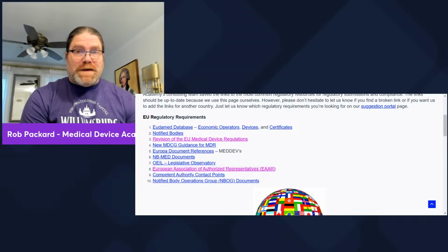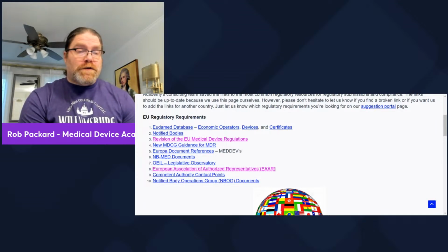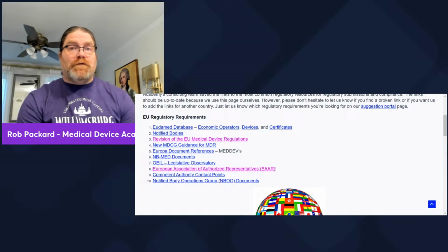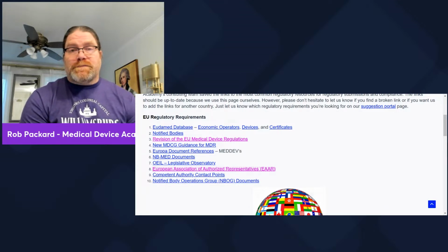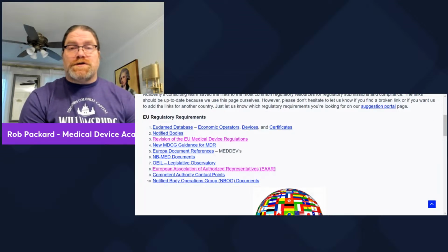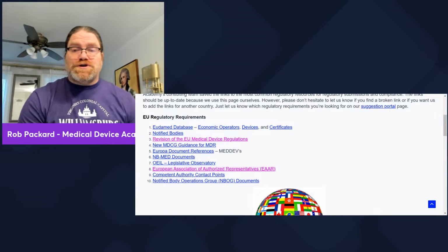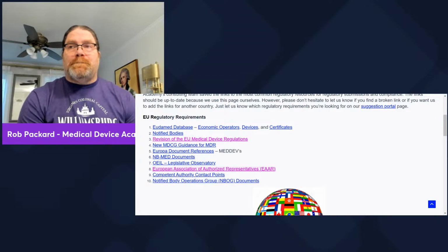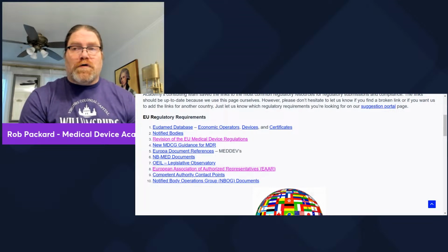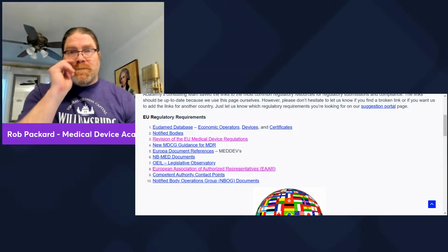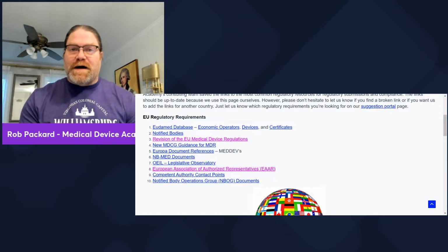There's a NANDO database, NANDO, for finding information about notified bodies and who the notified bodies are. You can sort that by different specialties. So if you're working on IVDs, only certain notified bodies will be on the list for NANDO for IVDs. If you have software as a medical device, only certain ones will be able to do software as a medical device. If you have sterile products, only certain ones can do sterile products. If you have animal tissues, human tissues, if you have a cardiac device that interacts with the heart in some way, those are all going to be different specialties, and they have different codes. And each notified body has to become qualified in that code.